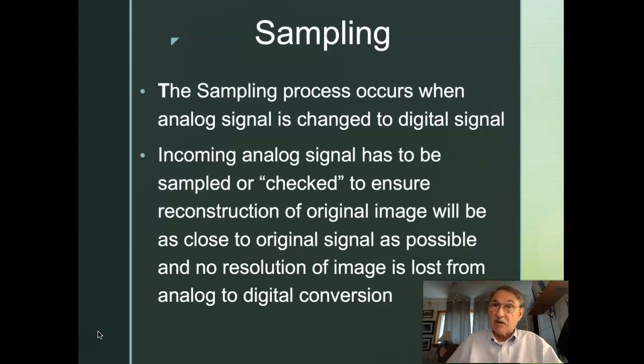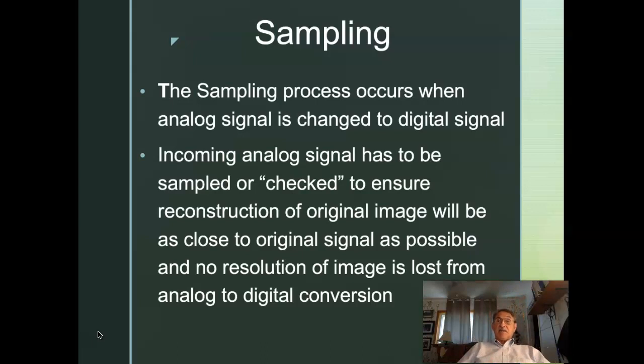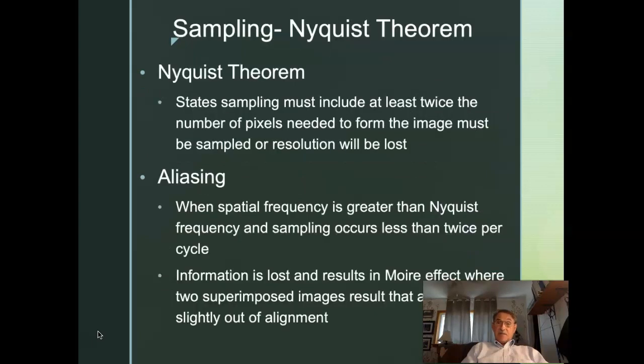As that process moves along, those various levels of exposure are assigned a binary number — a system of zeros and ones. We can take a very high exposure — very little attenuation — and assign it a number representative of a lot of exposure. Or something that's very light, which did not receive much exposure, is similarly assigned a digital number. This process of turning those values into representative numbers is part of sampling.